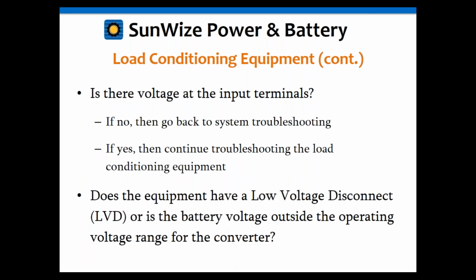Also, a lot of the inverters, not so many of the DC-DC converters, but a lot of the inverters, have a built-in low voltage disconnect. So you also might want to confirm that. If you do have voltage on the input, you might want to look at the LEDs and error lights on the inverter or converter and see if it's telling you that it might be a low voltage disconnect. You would also go back to that battery voltage measurement and see if the batteries are inside that LVD window for that inverter or converter.